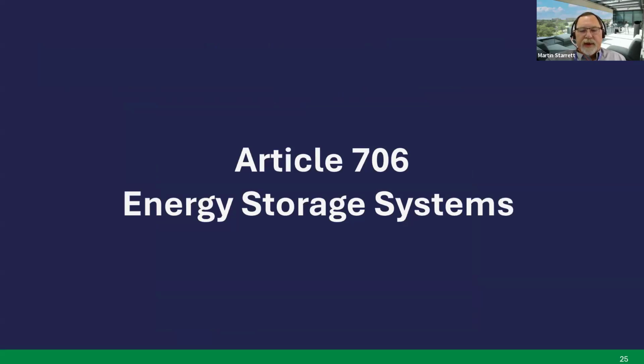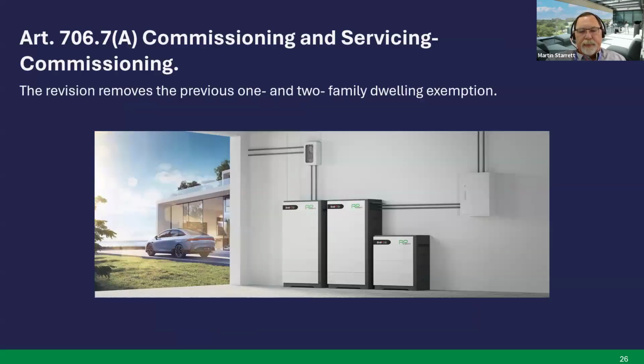Article 706, energy storage systems. So Article 706.7A, commissioning and servicing. The revision removes the previous 1 and 2 family dwelling exceptions. So the commissioning will be required for these two. It'll be per manufacturer's instructions.